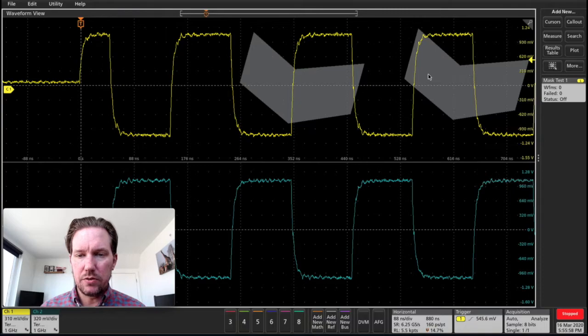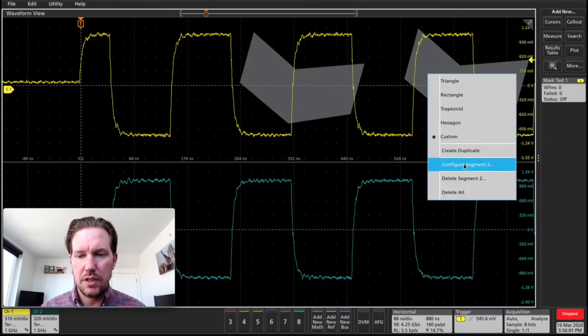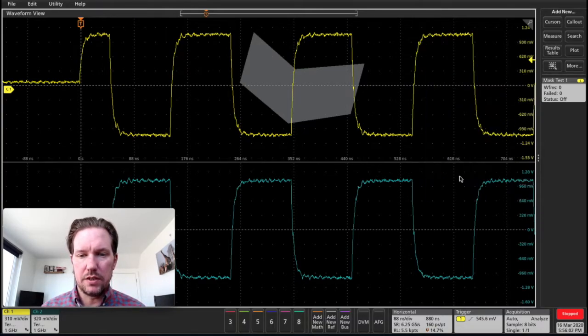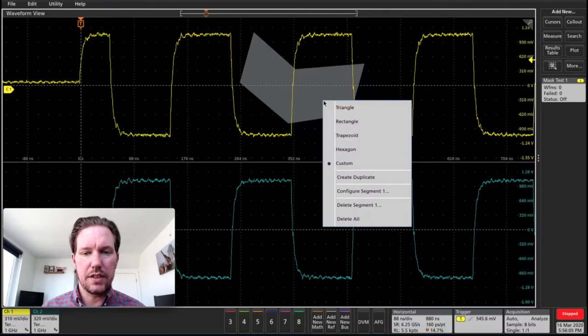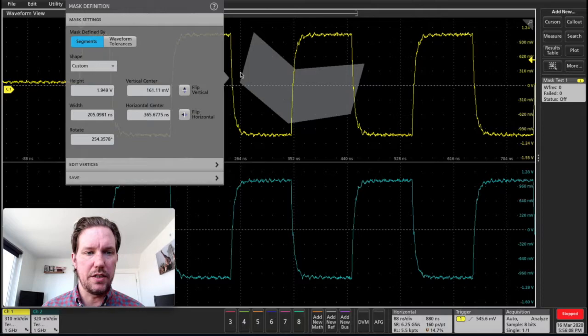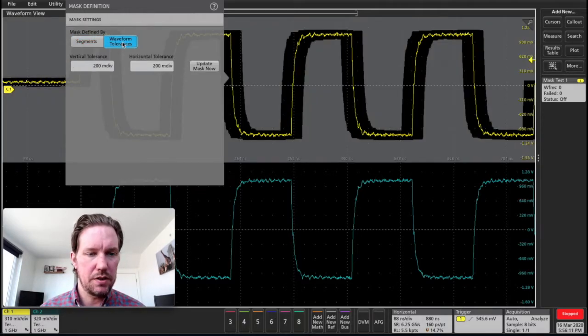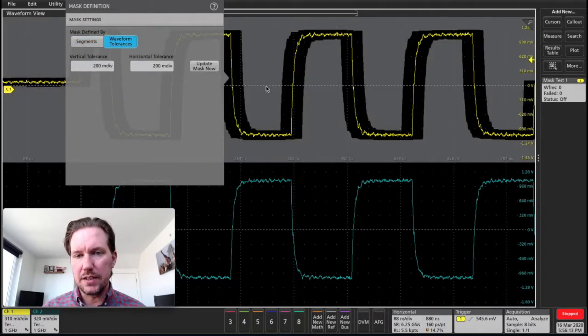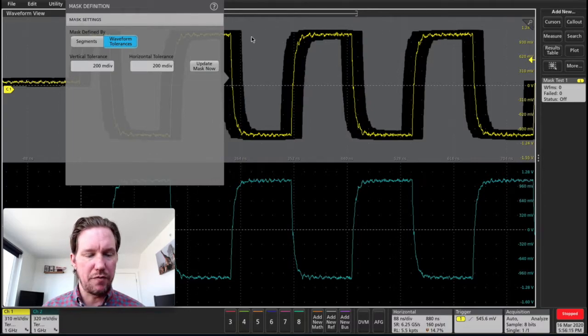But what I'm actually going to do for this demonstration is do the limit test. So if I click into this menu again, double tap in there, I'll go to waveform tolerances. And you can see I get this mask drawn around my waveform of interest.